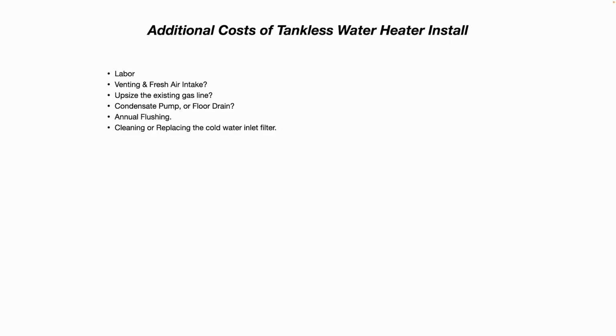So to avoid costly, expensive breakdowns of your tankless water heater, you really have to flush them once a year. You can use several gallons of vinegar and a little circulation pump where you hook up to the maintenance valves. Or you can buy an acidic descaler chemical, and then you mix that with water in a 5-gallon bucket. You have a sump pump that sits in there and it recirculates that descaler through the heat exchanger and gets rid of all that scale and mineral buildup. And again, you also need to clean and replace the cold water inlet filter, because if that clogs up or becomes too badly corroded, that will cause problems and error codes with your tankless water heater.